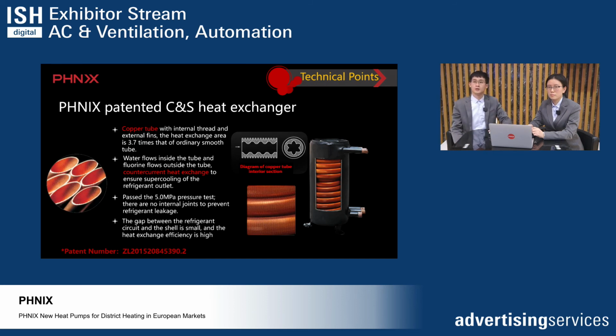Here we are using the PHNIX patented C&S heat exchanger, copper tube with internal thread and external fins. The heat exchange area is 3.7 times that of an ordinary smooth tube. Water flows inside the tube and refrigerant flows outside the tube, using counter current heat exchange to ensure supercooling of the refrigerant outlet. You can see on the right side the diagram of the copper tube interior section - the gap between the refrigerant circuit and the shell is small, and the heat exchange efficiency is high.